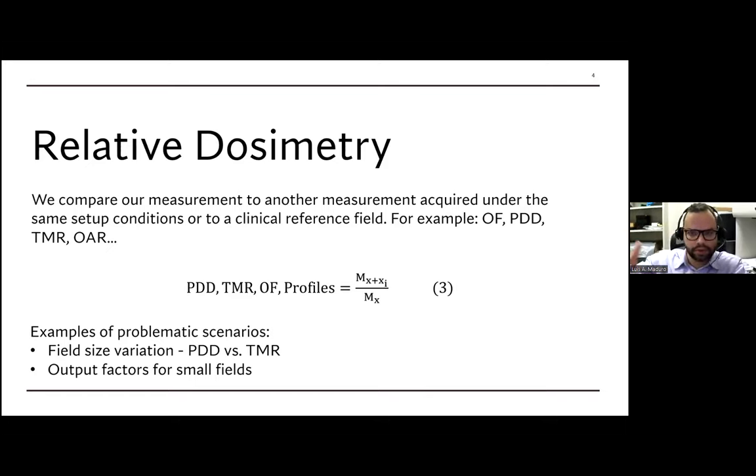To recap: for reference dosimetry, the challenge is not being able to achieve a 10x10 flat square field. For relative dosimetry, we need to account for the limitations emerging from field size in our relative ratios.